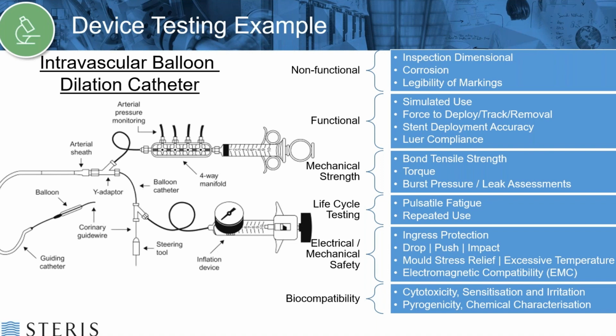Functional testing gets more into how the device performs and how successful the physician will be at using the device. Typical tests would include simulated use or bringing in an element of force measurement through deployment, track or removal testing. You can have stent deployment accuracy tests, which would be how accurately the stent can be positioned. And in addition to that, Luer testing would be key here, as you can see there are a number of Luer components associated with the assembly.